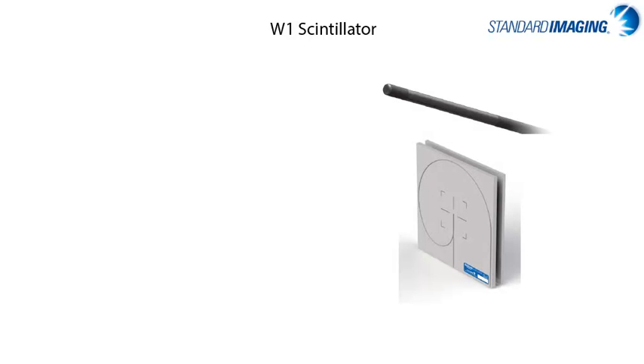Another instrument for interest of small field measurements, and only available from standard imaging, is the W1 scintillator. This scintillator is a 1 by 3 cylindrical BGO scintillating crystal attached to a fiber optic cable.